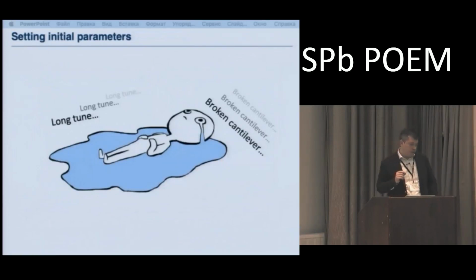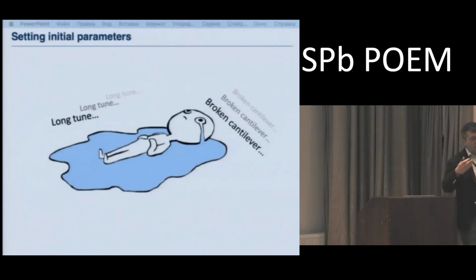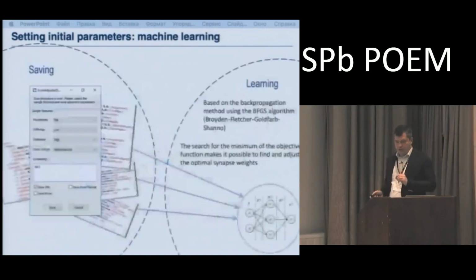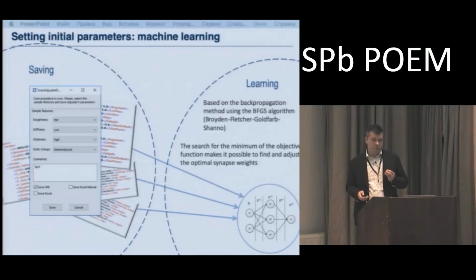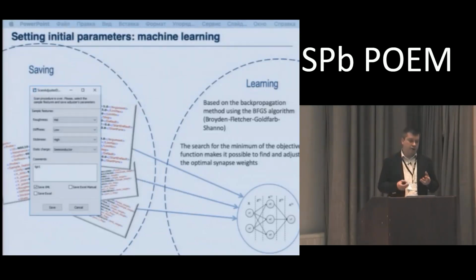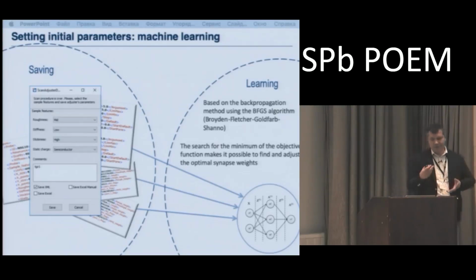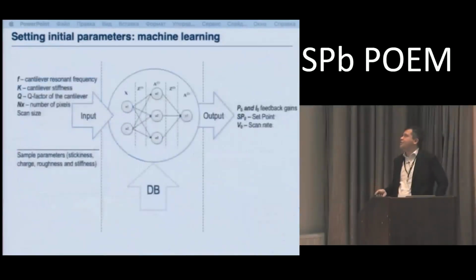Just one more note about it. If we start with the initial parameters that fit more, let's say, the atomically flat substrate, and we will start to scan some rough topography, this slide always takes a lot of likes during some online presentations. So when we start to scan some rough topographies, the cantilever might be damaged. So the selection of initial parameters is important, and the machine learning algorithms are useful here, like the engineer who knows, depending on if he has the rough topography sample or the flat sample, he knows it. And so the machine learning here solves this problem.